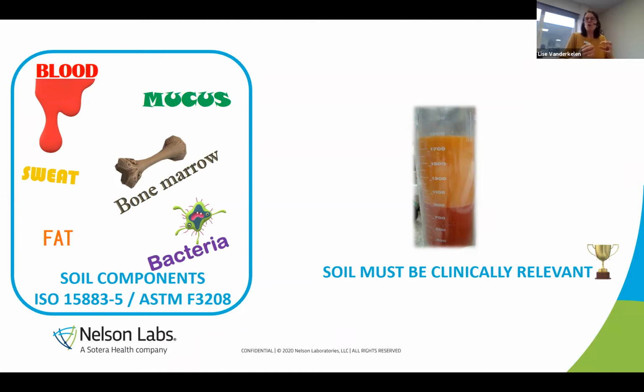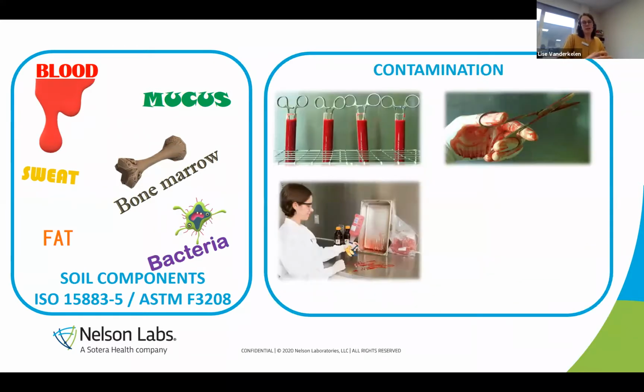You don't always need to follow standard test soil protocols or whatever. If you think that you need to add a certain soil component because it's relevant for your device, you just have to justify why you're going to use it. You have to do this justification anyway, and the soil must be clinically relevant. That is absolutely important. Then you decide how you're going to contaminate your device.